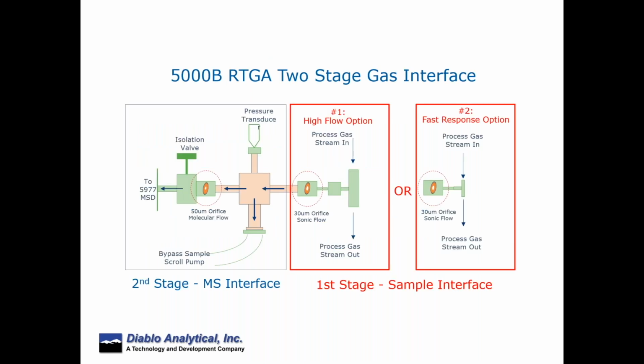So these are 2 of the interface options. The way to look at these is if you look at high flow option number 1, your process sample would enter through the T, the green T. You can see process gas in and process gas out. And then the bypass pump, you can see the sample flows through an orifice to a cross, and then the bypass pump sucks the sample across an orifice.